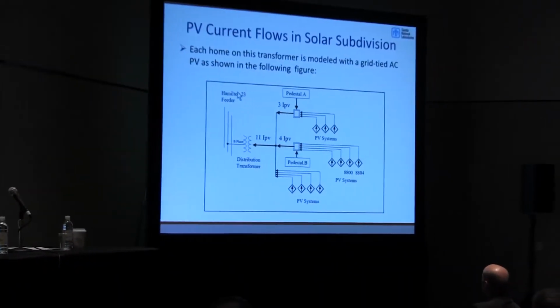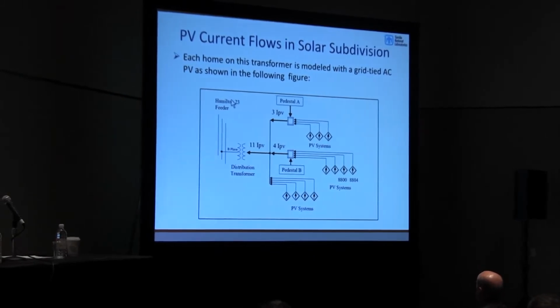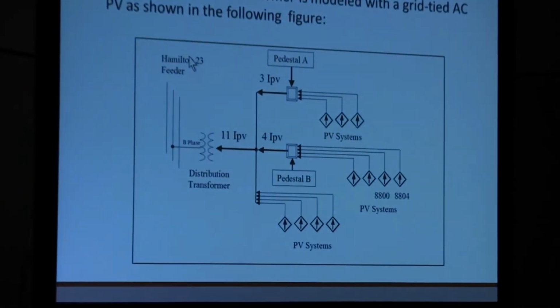So one of the things that we did in New Mexico is we evaluated a subdivision. I won't go into all the details here, but this is basically how you go about doing it. We evaluated a solar subdivision with a 50 kVA transformer. That's what you see off on the left. And this was 11 homes. And we basically did all the analysis on what the secondary circuit looked like, the types of triplex cable, the number connected to a pedestal, and also looked very importantly at the standard utility operating practices. Once you put that model together, you get a PV current flow model that looks something like this, where you can see where all the various voltage rises are going to occur on the distribution transformer. So in this case, we had 11 homes, and I'll have you take note of the far right current input, which is at node 8804.